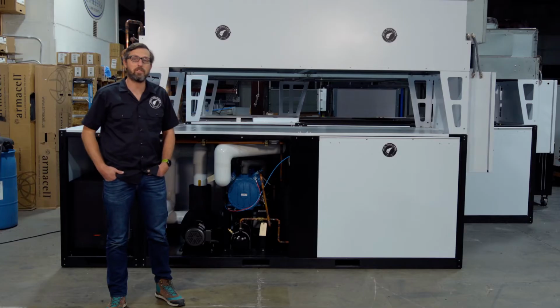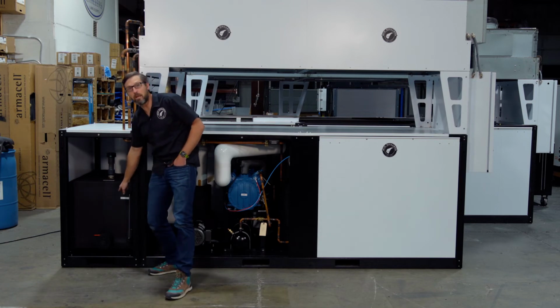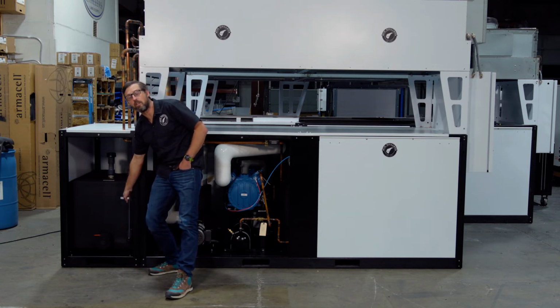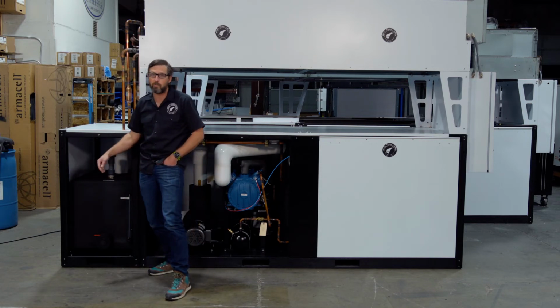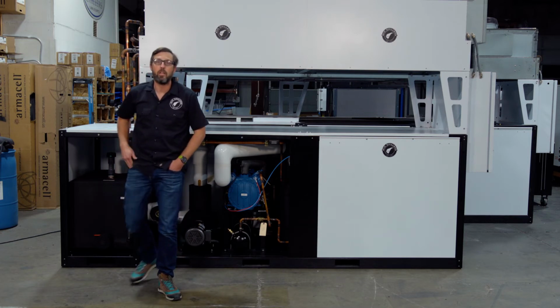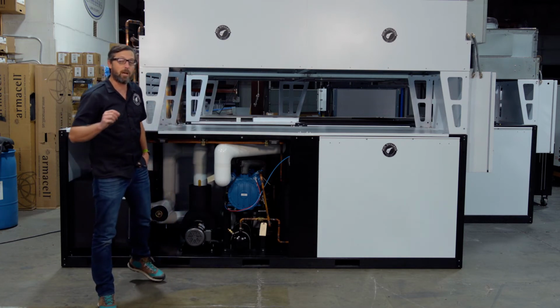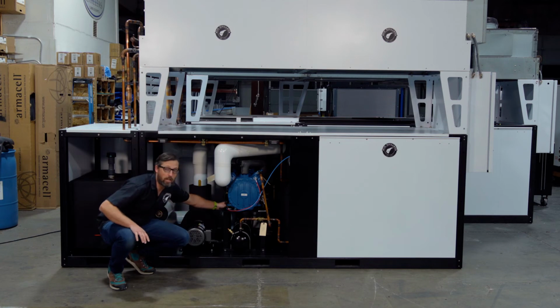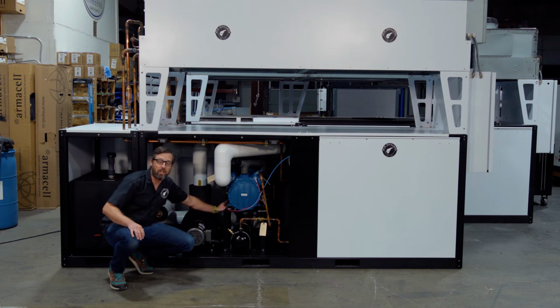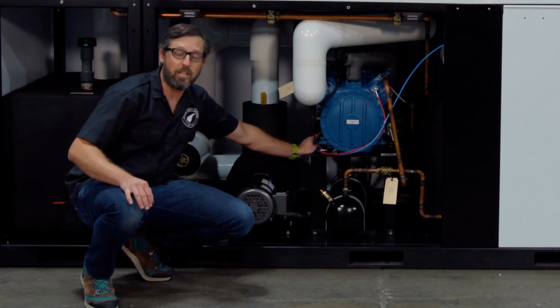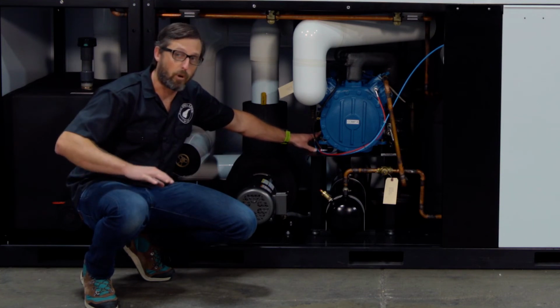Alright, now that you let the Dynalene pump run for about 30 minutes, cycling Dynalene HC50 throughout your entire piping system, we're going to come back and make sure that the minimum level is still ensured here in the reservoir. If it's not, just add a little bit more Dynalene until you're above that level. Once you've done that, we're going to come back and double check one more time the oil level in each of the sight glasses on each compressor in your unit. We want to ensure that there is oil in this before we move forward.